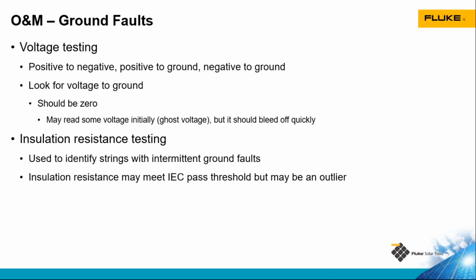That's much greater than the 1 megaohm minimum required by the IEC standard, but still less than what the other circuits were testing at. When I looked at that array further, I found an interconnection between two modules, the MC4 type connectors, laying in a puddle on the roof. So it wasn't a ground fault at that point, but we were definitely losing some current to ground. Once I removed the connector from the puddle, reattached the wires to the racking and let it dry out for a little bit, I retested that circuit and it was up at 1 gigaohm, equal to that of the rest of the circuits on that system.